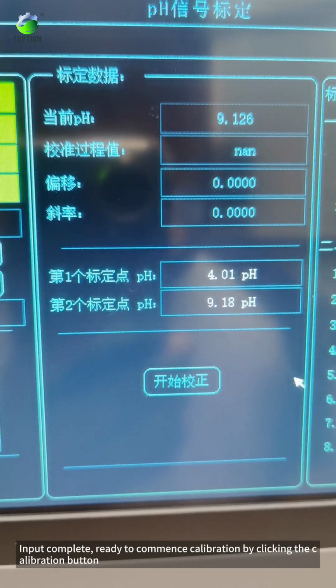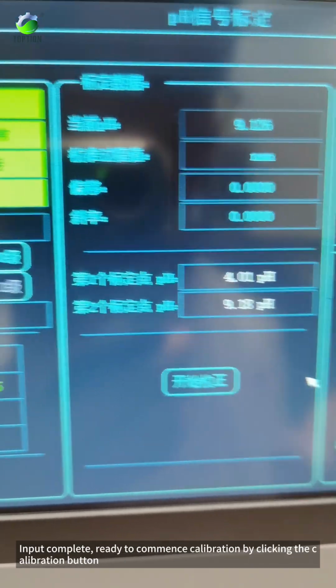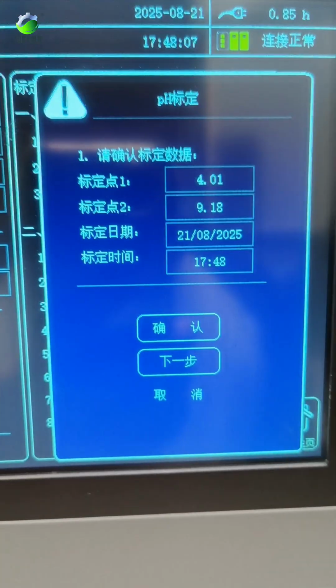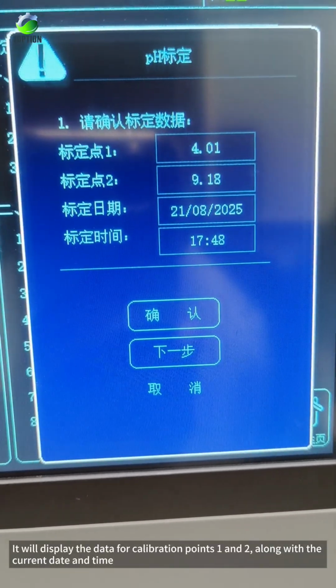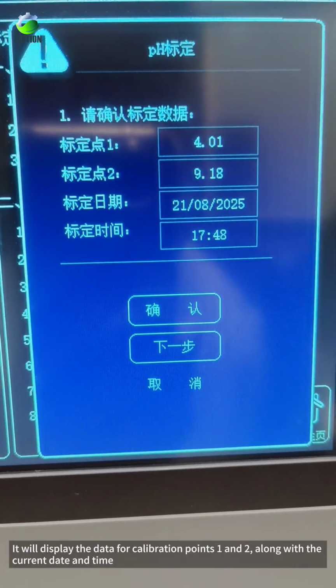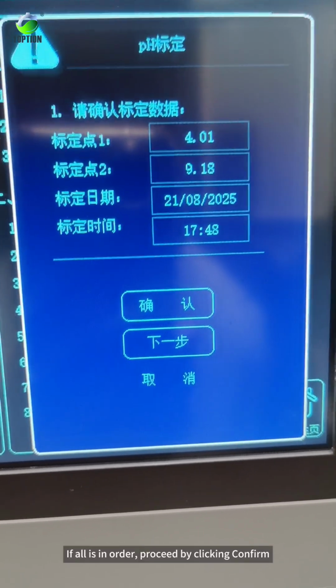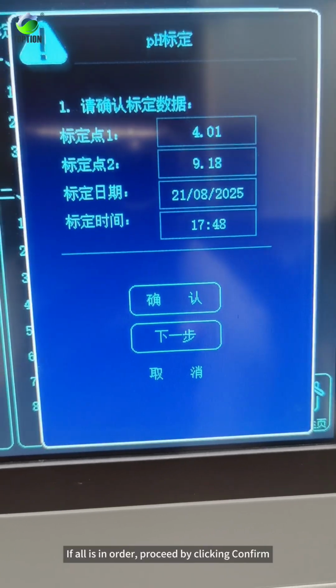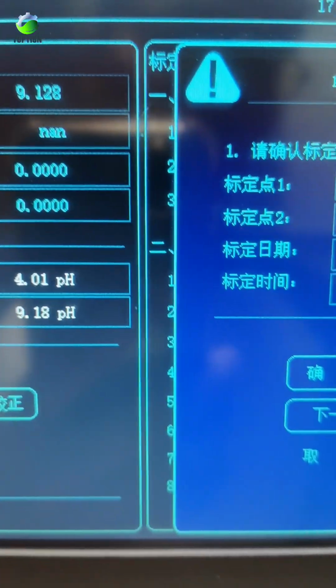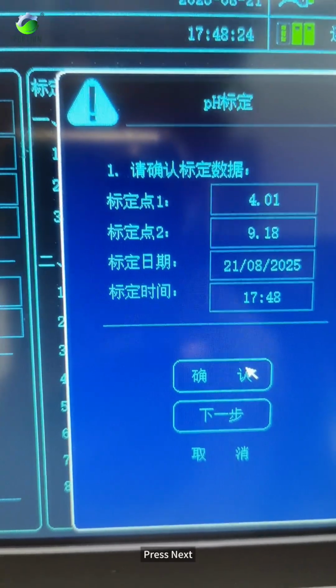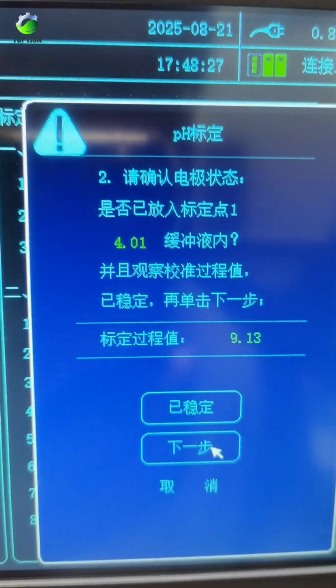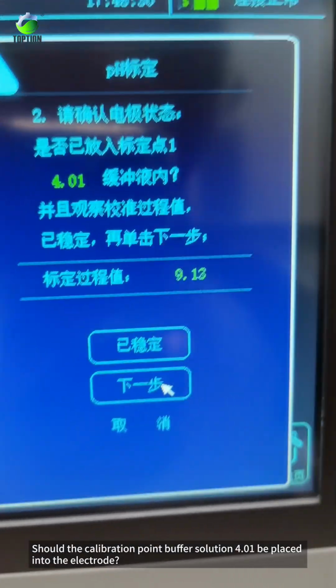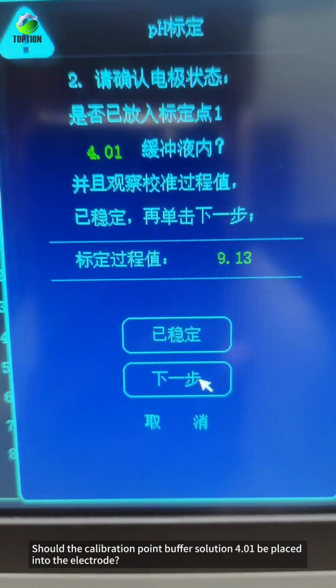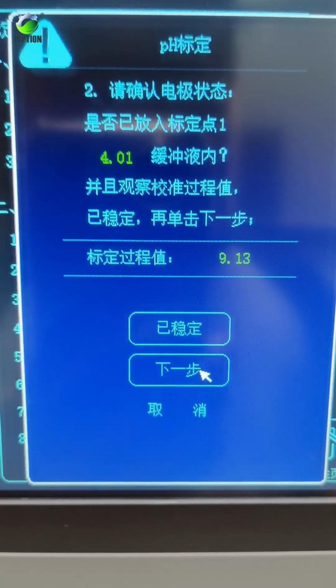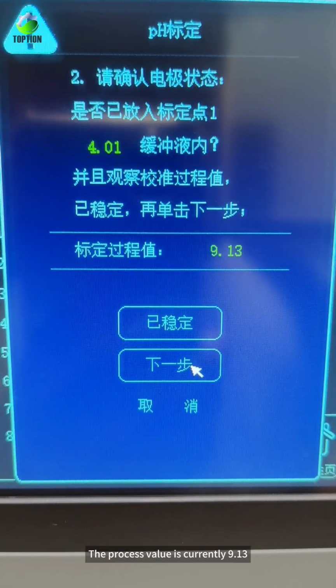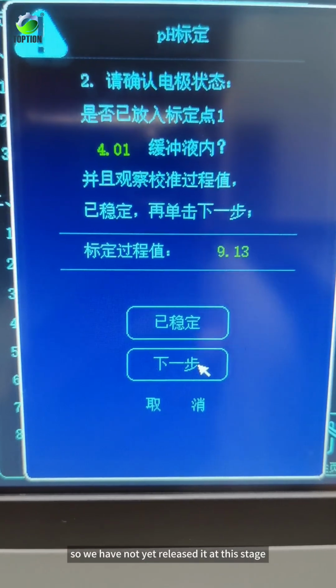Input complete, ready to commence calibration by clicking the calibration button. It will display the data for calibration points 1 and 2 along with the current date and time. If all is in order, proceed by clicking Confirm. Press Next. Should the calibration point buffer solution 4.01 be placed into the electrode? The process value is currently 9.13, so we have not yet released it at this stage.